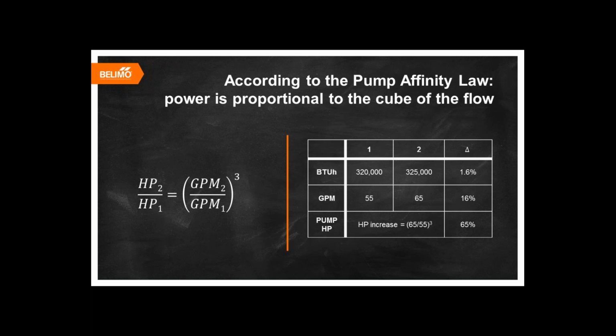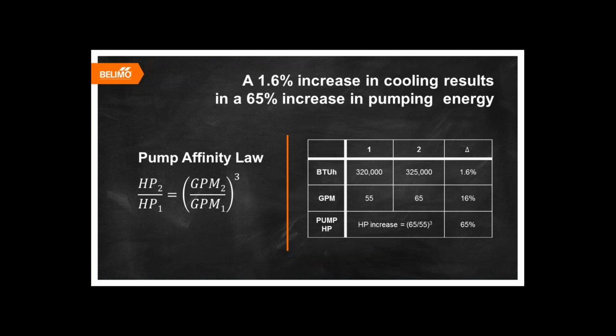As we can see, for point 1 we have our 320,000 BTUs at a flow of 55 gallons per minute. Point 2 was 325,000 BTUs at 65 gallons per minute. We enter them into the pump affinity rule to determine the additional horsepower that's needed. Because of the cubed ratio of the pump affinity rule, we find that a 1.6% increase in cooling results in a 65% increase in pumping energy.